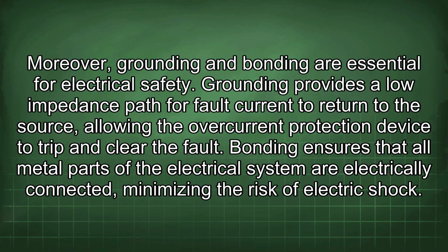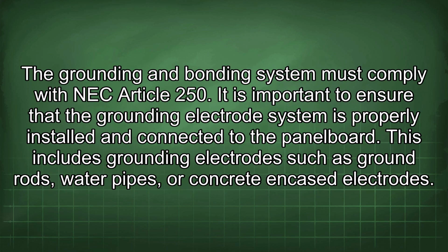Moreover, grounding and bonding are essential for electrical safety. Grounding provides a low impedance path for fault current to return to the source, allowing the overcurrent protection device to trip and clear the fault. Bonding ensures that all metal parts of the electrical system are electrically connected, minimizing the risk of electric shock. The grounding and bonding system must comply with NEC Article 250. It is important to ensure that the grounding electrode system is properly installed and connected to the panel board. This includes grounding electrodes such as ground rods, water pipes, or concrete encased electrodes.